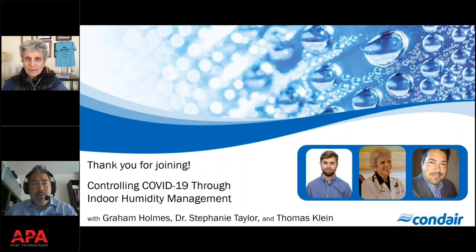We're always going to give you a design where, typically, most designs say, I want to come off the evaporator at 55 degrees. So maybe we'll have to go into that section at 75 degrees. But you're going to know in the design phase what the temperature drop could be at maximum output. Then we implement enthalpy control, and APA does this, and they've done it quite successfully, and they can help you with that. But yes, the temperature drop is what we have to account for. But that's the same temperature drop that actually helps us during an economizer day.